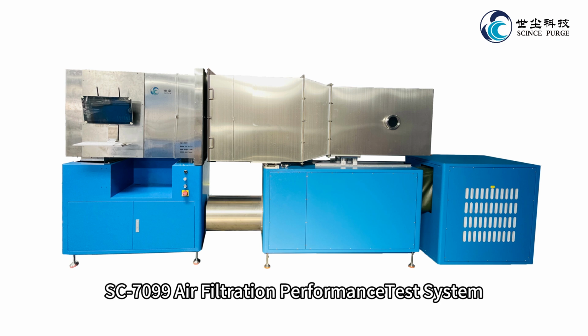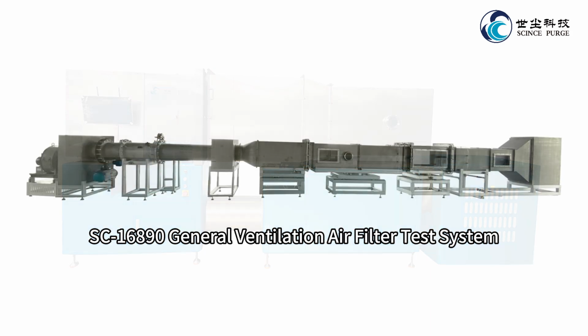Models SC-16890, SC-7099. Description: used for measuring the overall efficiency of general ventilation filters, supporting standards such as ISO 16890, EN 779, and ASHRAE 52.2. The efficiency measurement range exceeds standard requirements. This equipment also provides overall efficiency testing for EN 1822-5 and ISO 29463-5, with capabilities up to H14 at 0.3 micrometers.